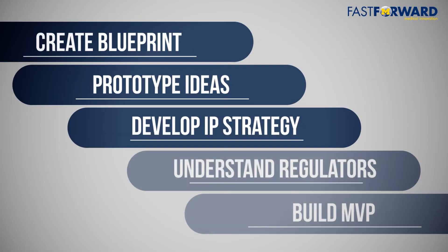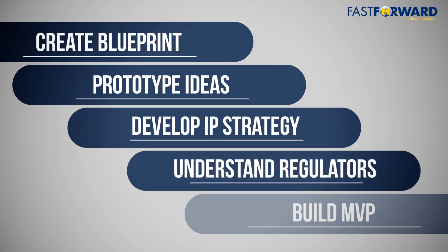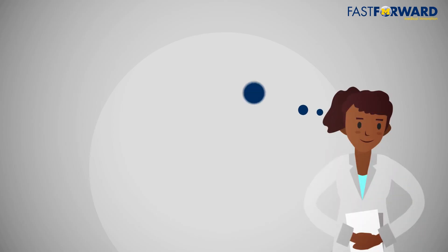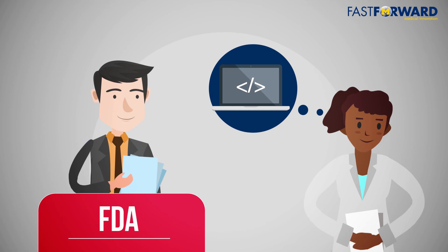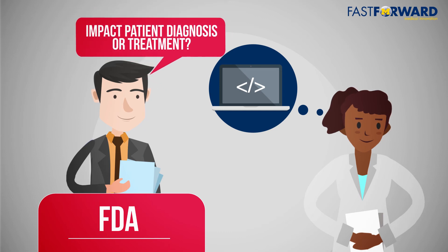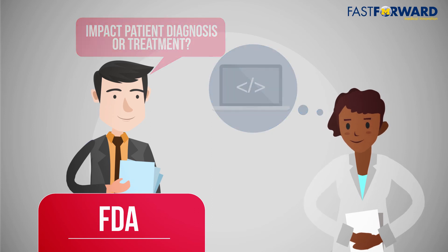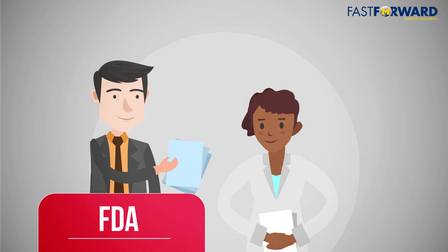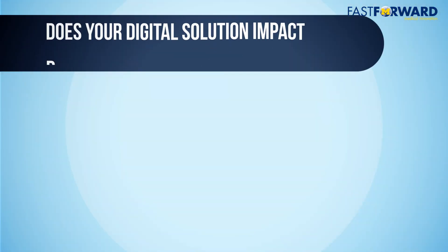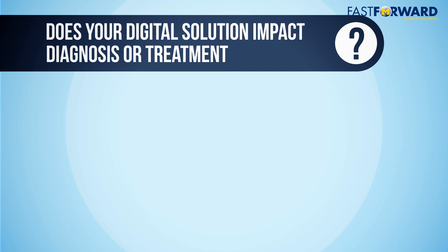The third step in the roadmap is to look at how regulatory considerations from the FDA and HIPAA will impact your development plan. First, you need to determine if the FDA will have purview over your digital health technology. The FDA regulates medical technologies that have the potential to impact patient diagnosis or treatment. For a general guideline, you can follow this series of questions, but make sure to seek guidance from a regulatory professional to confirm your plan. Does your digital solution diagnose or provide clinician decision support? If your technology treats, diagnoses, or provides decision support, the FDA may retain the right to regulate your technology.